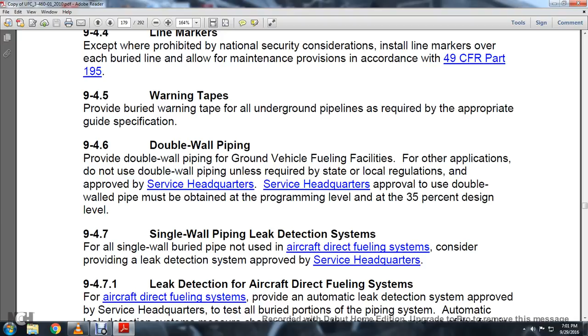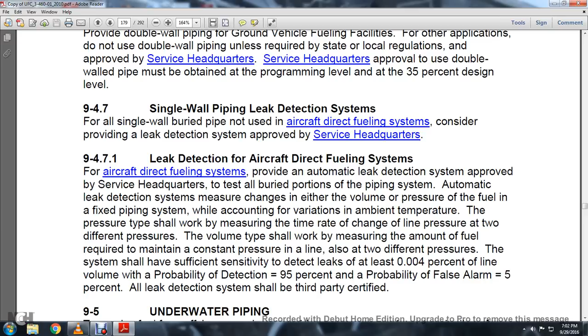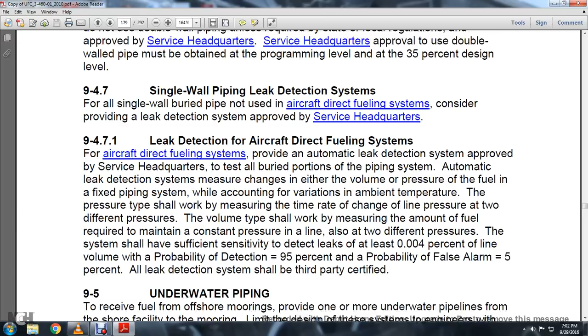Automatic leak detection systems measure changes in either the volume or the pressure of the fuel in a fixed pipe system while accounting for variation in ambient temperature. The pressure type shall work by measuring the time rate of change of the line pressure at two different pressures. The volume type shall work by measuring the amount of fuel required to maintain a constant pressure in the line, also at two different pressures. The system shall have sufficient sensitivity to detect leaks of at least 4 thousandths percent of the line volume, with a probability of detection of 95% and a probability of false alarm of 5%. All leak detection shall be third party certified.